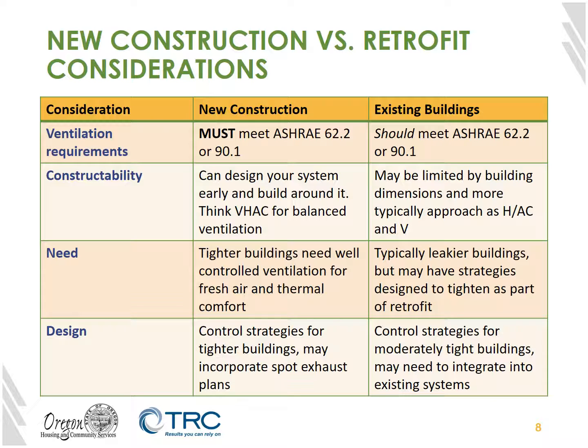Beyond basic efficiencies and whether or not you're using an HRV or an ERV, there are also some other considerations that need to be taken into account that may really be different between a new construction building and an existing building. For instance, in new construction buildings, depending on if you're building a low-rise or mid to high-rise building, you're going to be required to meet ASHRAE 62.2 or ASHRAE 90.1. These are ventilation standards brought to you by the American Society of Heating, Refrigeration, and Air Conditioning Engineers. These are designed, again, to make sure that these tighter buildings are properly ventilated. 62.2, on the other hand, is really focused for low-rise multifamily and single-family homes.